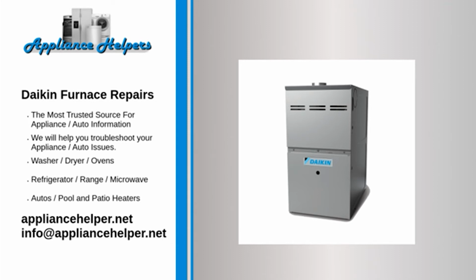Furnace blowing cold air. If the furnace won't produce heat, you can check to see if it is getting power by moving the fan switch from the auto position to the on position. If the fan comes on, then the furnace is getting power. The likely issues then are: the gas is turned off, so check the gas cock near the furnace to make sure it is parallel to the gas line; the gas control valve isn't opening and must be replaced; the igniter is failing and must be replaced.